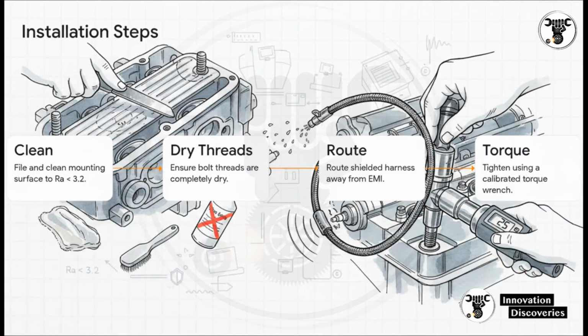So to guarantee accurate acoustic coupling, your workflow has to be rigorous. No cutting corners. First, file and clean that mounting surface until the roughness is under 3.2 micrometers. Second, make absolutely sure the bolt threads are bone dry. No thread locker, no sealants. Liquids act as acoustic dampeners. Third, route your shielded harness far away from EMI sources, like the alternator. And fourth, always, and I mean always, tighten that bolt strictly using a calibrated torque wrench.